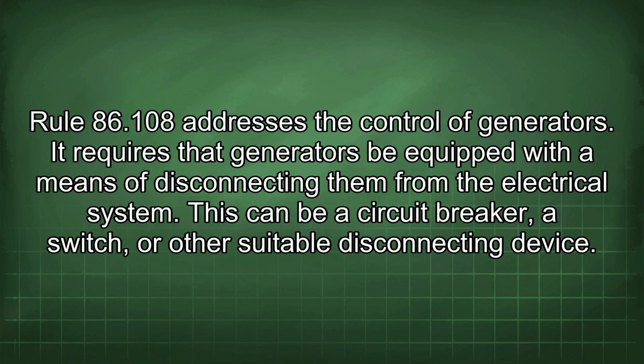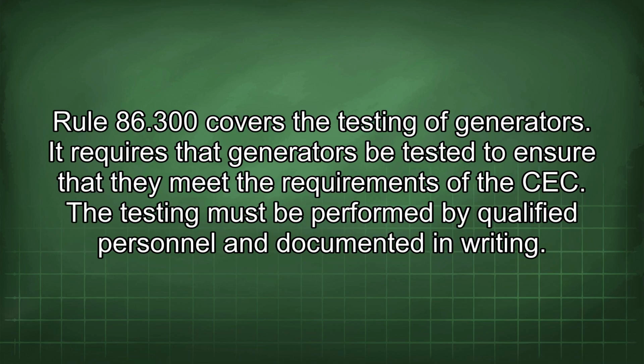Rule 86.108 addresses the control of generators. It requires that generators be equipped with a means of disconnecting them from the electrical system. This can be a circuit breaker, a switch, or other suitable disconnecting device. Rule 86.300 covers the testing of generators. It requires that generators be tested to ensure that they meet the requirements of the CEC. The testing must be performed by qualified personnel and documented in writing.